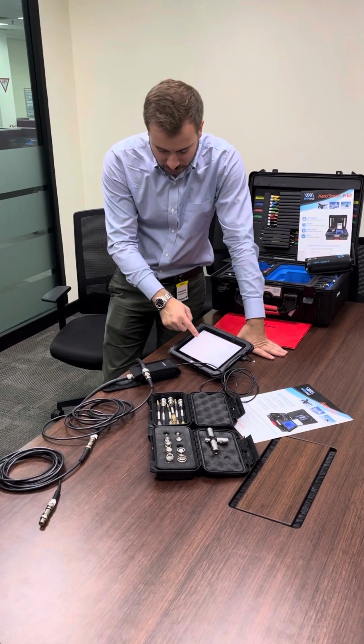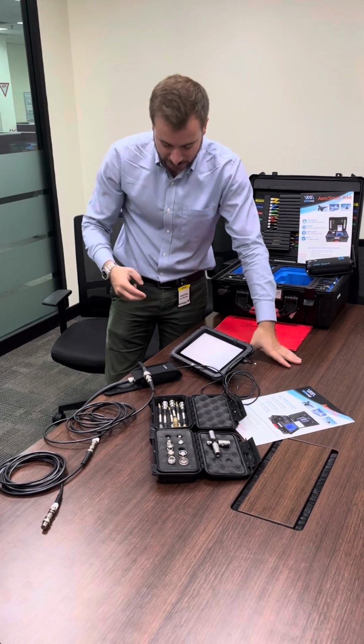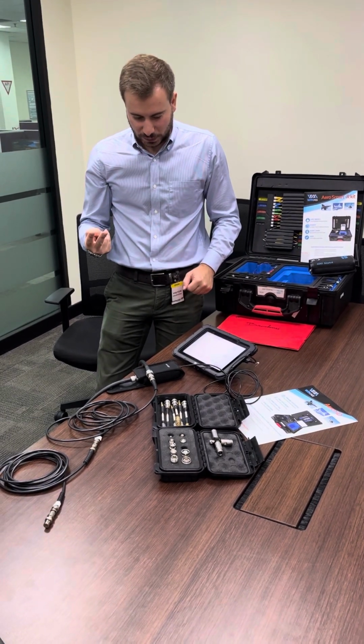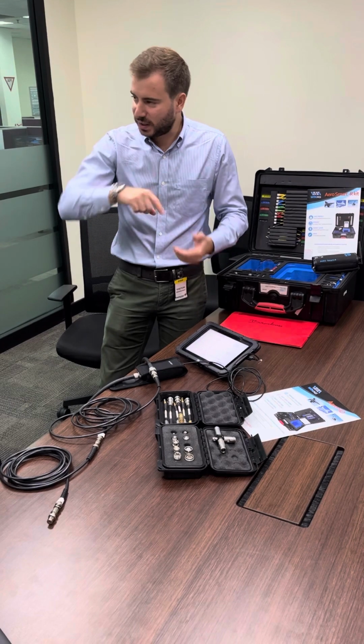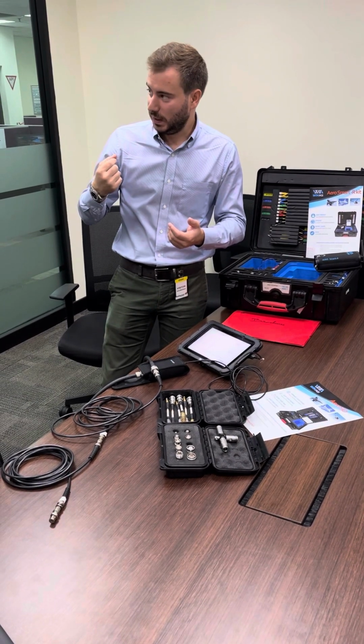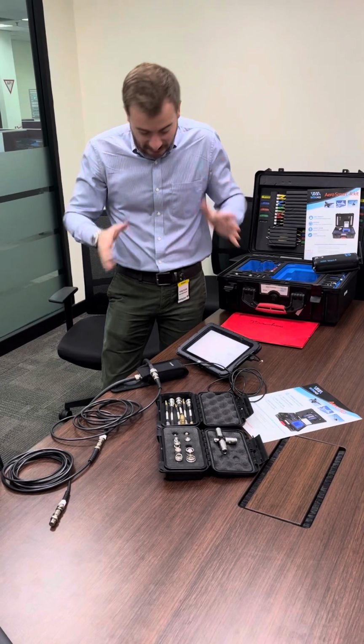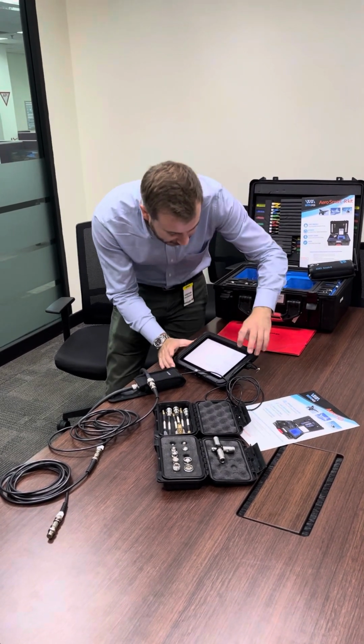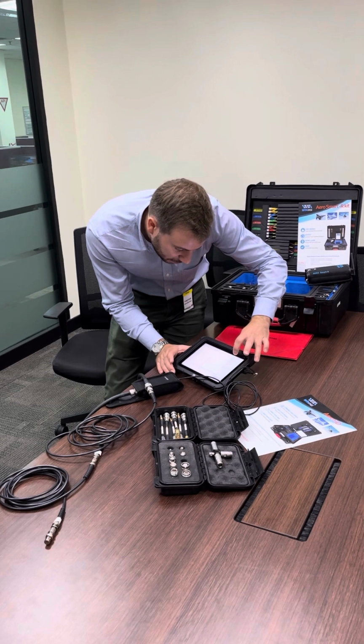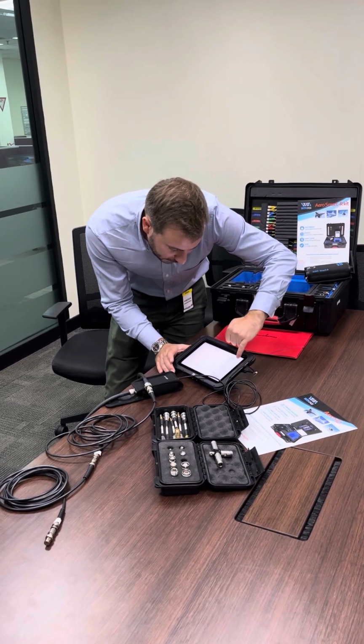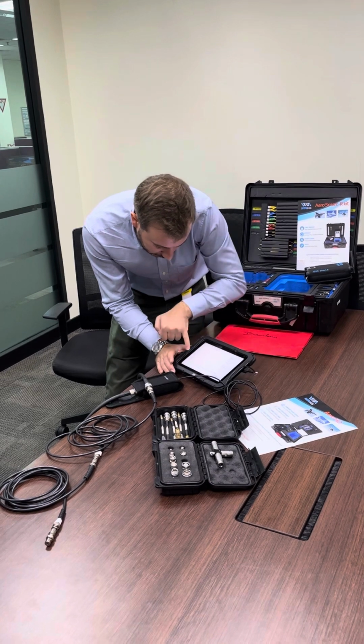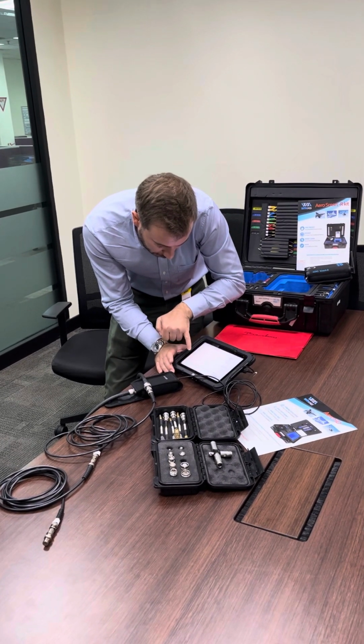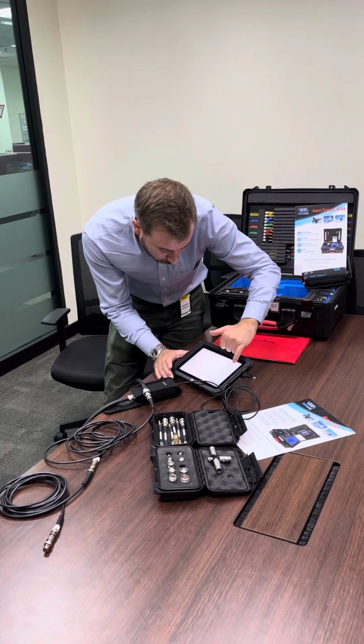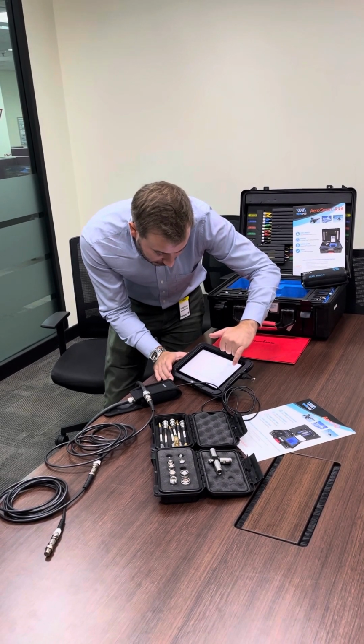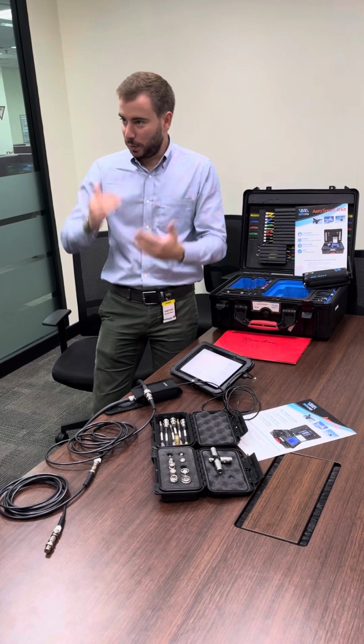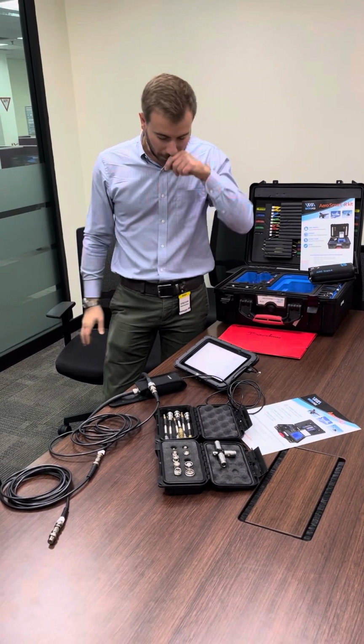Now it applies when you have 2 lines up, because now it applies the other tolerance from Airbus, which counts the number of peaks. That's the tolerance from Airbus. So here it will say, let me check, max peak. It counts one peak, which is here actually, okay? One peak in between 1.09 and 1.13. So it will count the number of peaks.